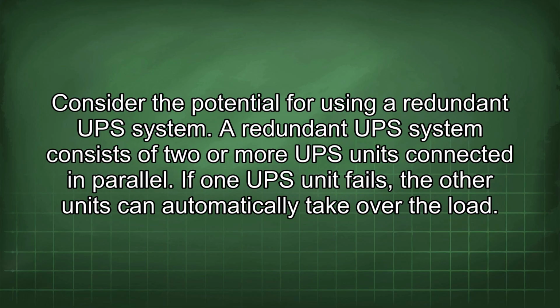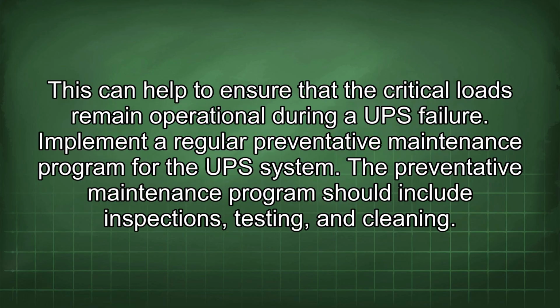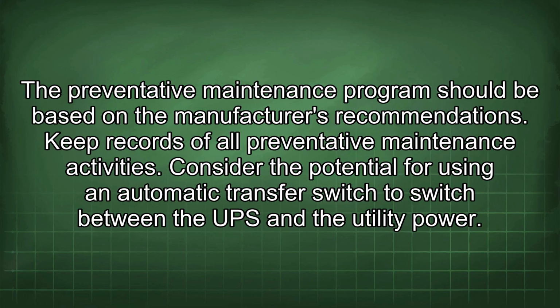Consider the potential for using a redundant UPS system. A redundant UPS system consists of two or more UPS units connected in parallel. If one UPS unit fails, the other units can automatically take over the load. This can help to ensure that the critical loads remain operational during a UPS failure. Implement a regular preventative maintenance program for the UPS system. The preventative maintenance program should include inspections, testing, and cleaning. The preventative maintenance program should be based on the manufacturer's recommendations. Keep records of all preventative maintenance activities.